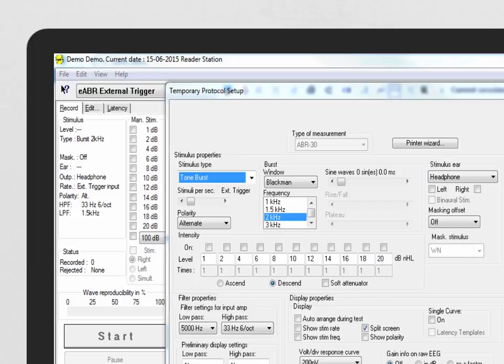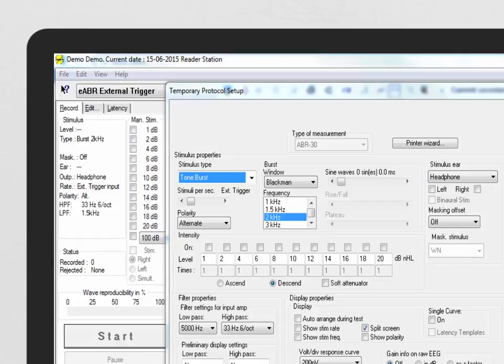In addition to setting the stimuli per second, it is also important to select headphone from the transducer list. Even though the cochlear implant is the actual transducer, if the alternative option of inserts is selected, then the software will incorrectly subtract 0.9 milliseconds from the recording.